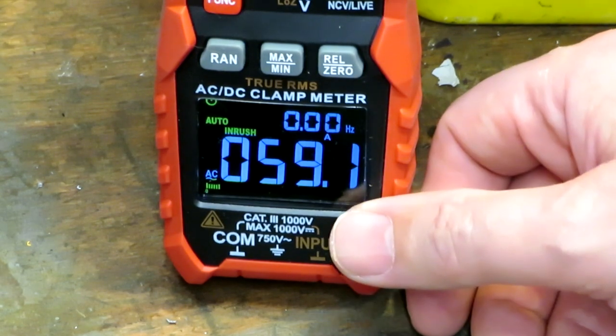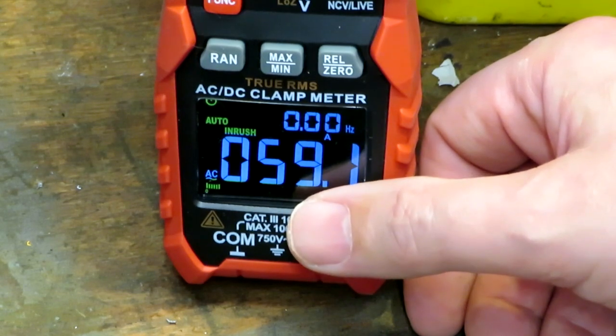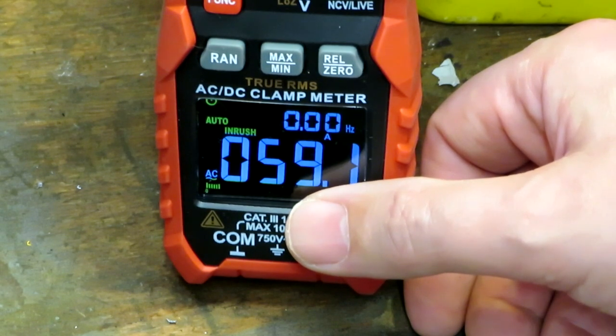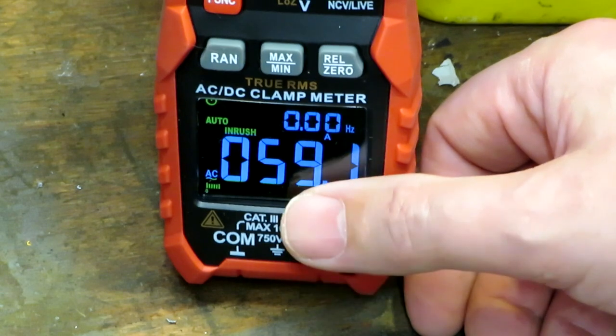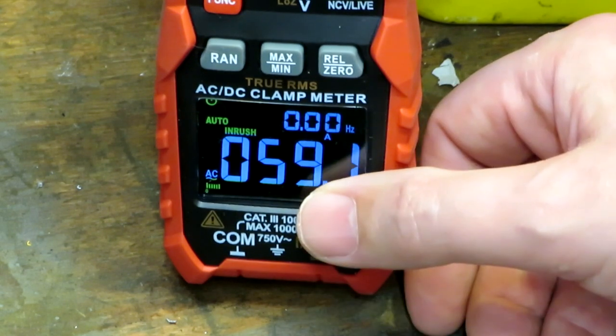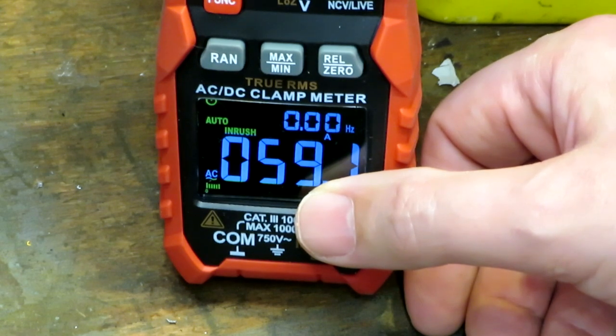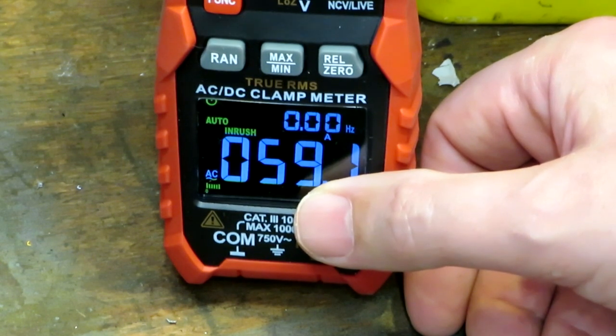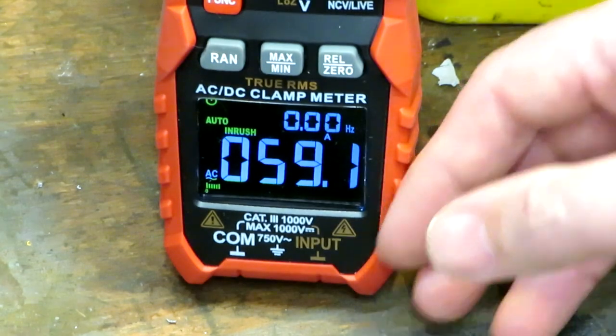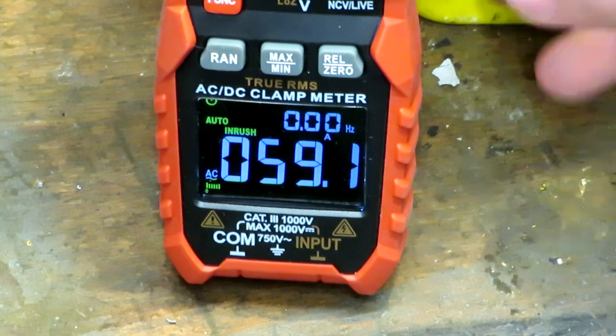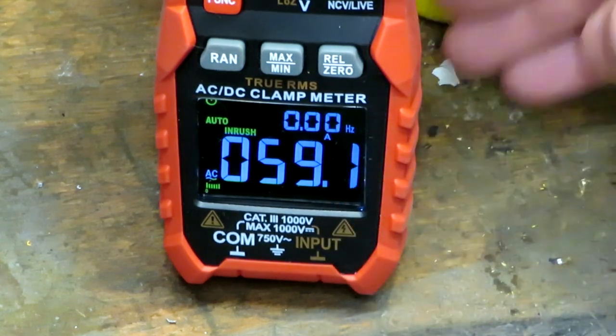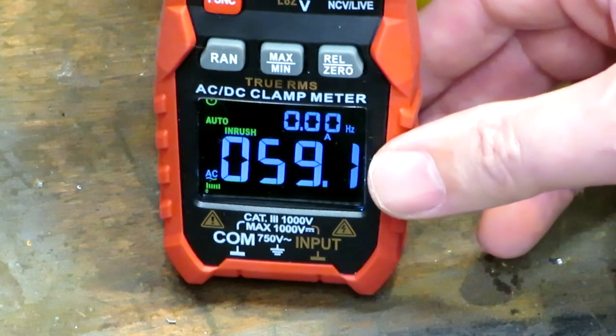Now when you switch on and off the transformer, you can actually get quite a variance in the inrush current because it depends at what part of the voltage cycle you are when you actually switch the transformer on. If you're at the zero crossing point, you'll find that the inrush current will be quite low. But if you happen to be at the top of the 240 volt waveform when you switch the transformer on, that 240 volts is applied directly across the transformer windings. Now there isn't actually a magnetic flux there at the time, so that transformer winding doesn't look like an inductor, it actually just looks like a piece of wire. It takes time for the magnetic field to build up within the transformer, so that's why you get such a high inrush current, but as soon as the actual core has been magnetised, very quickly that current drops away.